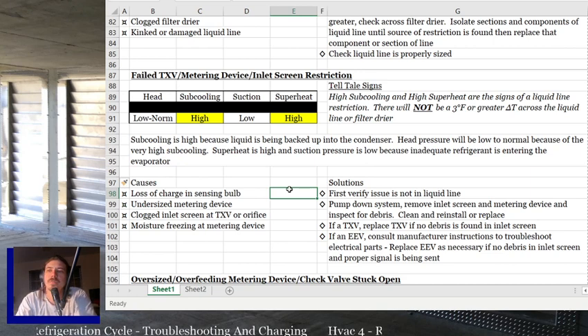If it's a TXV, replace the TXV if no debris is found in the inlet screen. Probably just replace the TXV anyway. If you've got a failed TXV, I've seen them where they're only kind of failing, but you've got high superheat and good or high subcooling, just replace the TXV. If superheat's too high, replace it. If superheat's too low, replace the TXV. Anytime you've verified that the issue's at the TXV, just replace it, especially if it's non-adjustable. If it's an adjustable TXV, you might be able to adjust it, but most of us deal with non-adjustable TXVs.